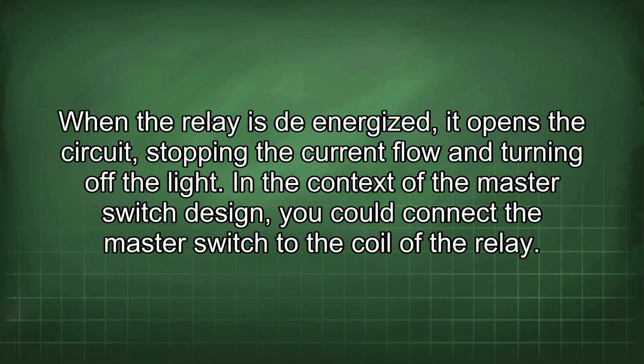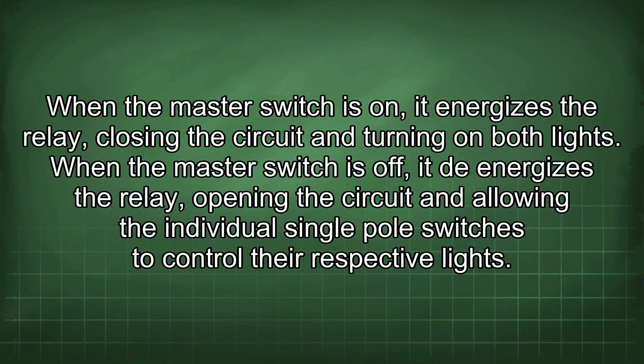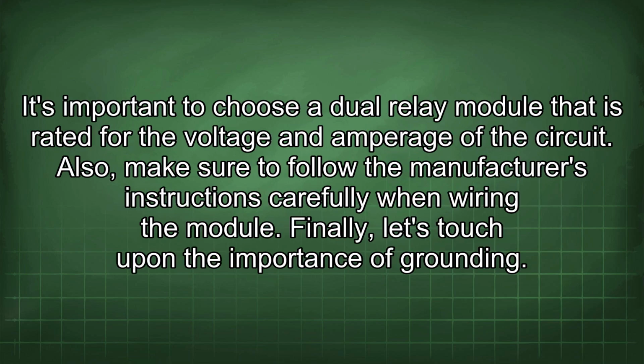In the context of the master switch design, you could connect the master switch to the coil of the relay. When the master switch is on, it energizes the relay, closing the circuit and turning on both lights. When the master switch is off, it de-energizes the relay, opening the circuit and allowing the individual single-pole switches to control their respective lights. It's important to choose a dual relay module that is rated for the voltage and amperage of the circuit. Also, make sure to follow the manufacturer's instructions carefully when wiring the module.